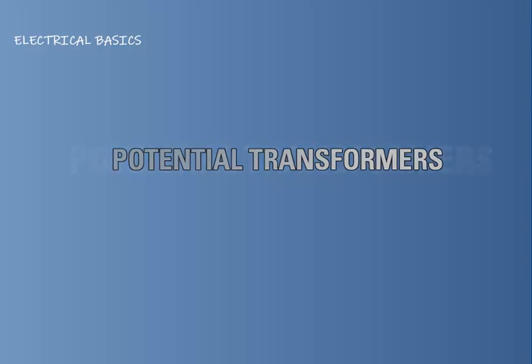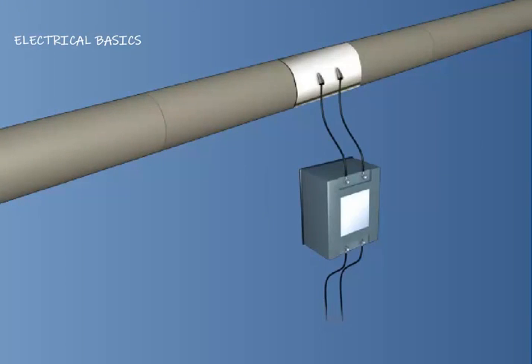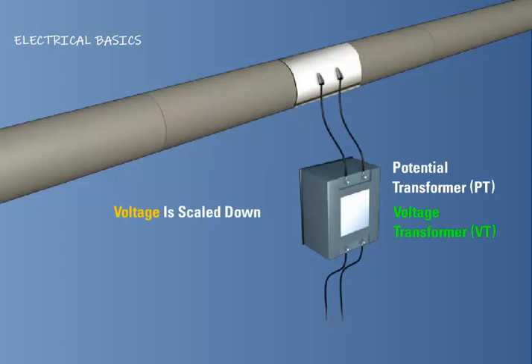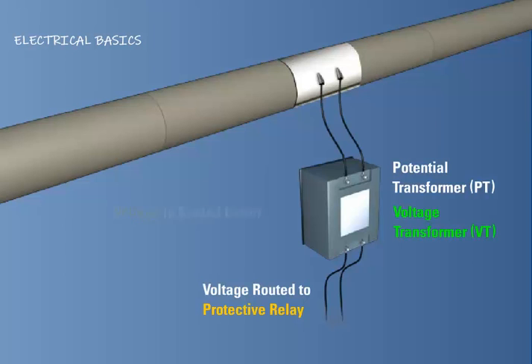The next type of transformer we will cover is the potential transformer, symbolized as PT, or sometimes known as voltage transformers, symbolized as VT. Similar to current transformers, potential transformers scale down the voltage passed through them, as opposed to current. The scaled-down voltage is then routed to a protective relay for measurement. A PT is classified with a conversion ratio indicating the amount the primary voltage is scaled down.